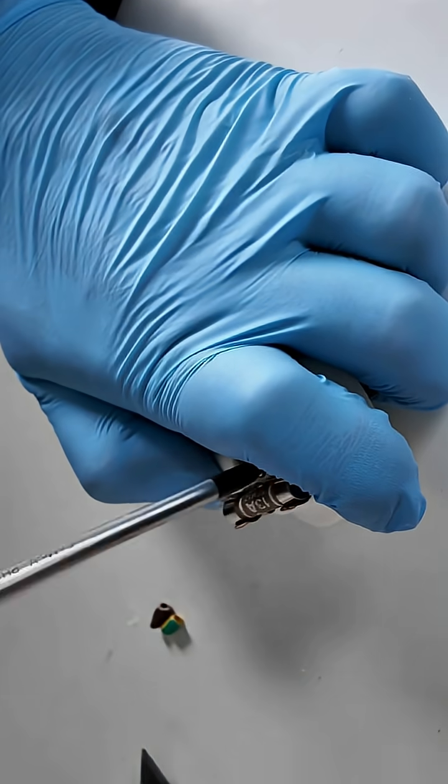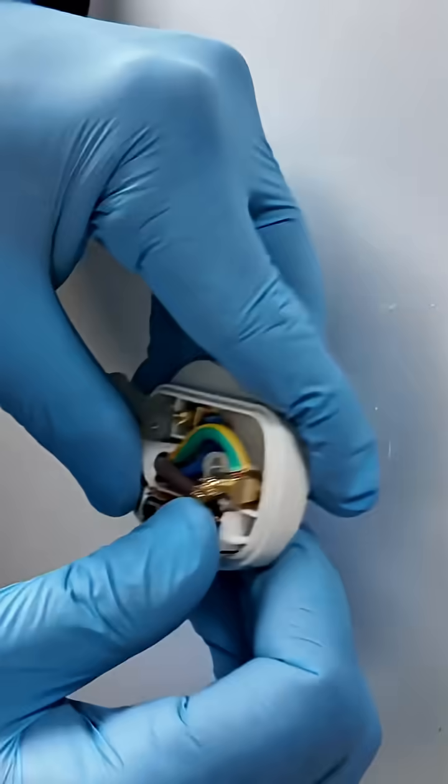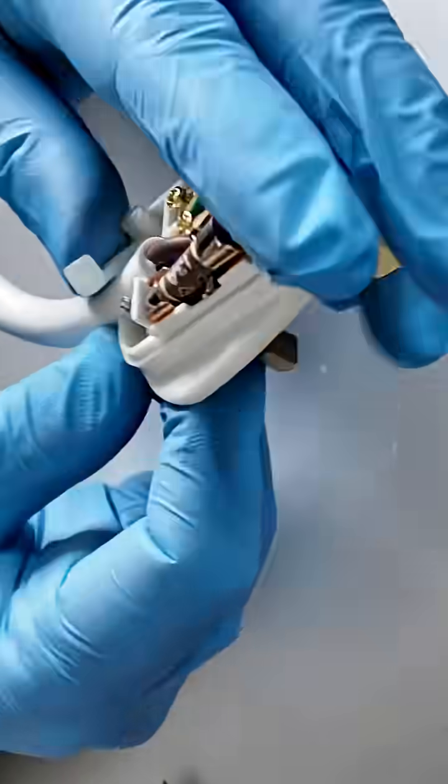It's important: no bare copper should be visible outside the terminal. The earth wire is slightly longer, so it stays connected if the cable is pulled.